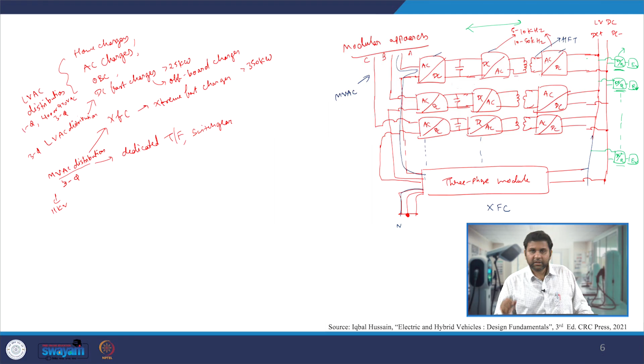So DC-DC creates a DC link, then DC-AC will convert the DC link into the high frequency AC, which is seen by the transformer. Because of the transformer action at the output secondary, you will have the high frequency AC, which gets converted into DC and then connected to the low voltage DC bus. And from the low voltage DC bus, individual EVSEs will have the DC-DC converter. So you can have the low voltage distribution line, and then a dedicated DC-DC converter which will be connected to the EV, and that's when the EV can be charged.